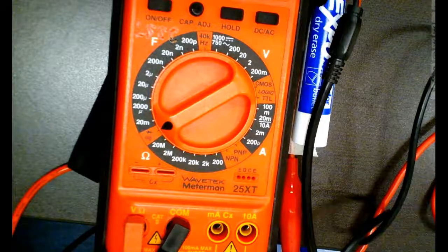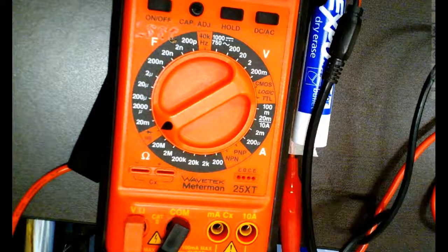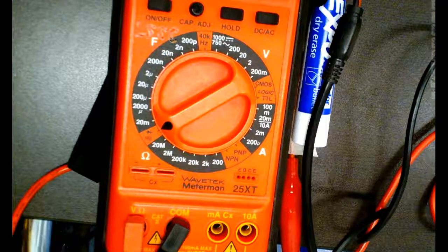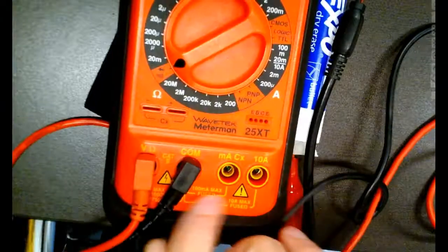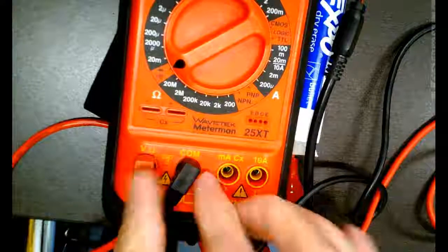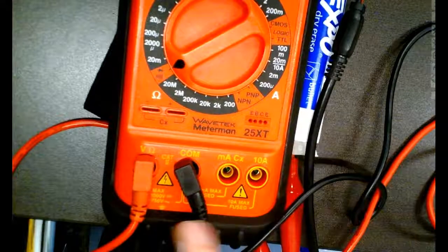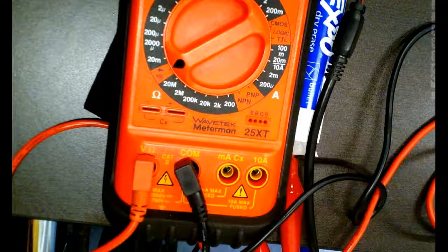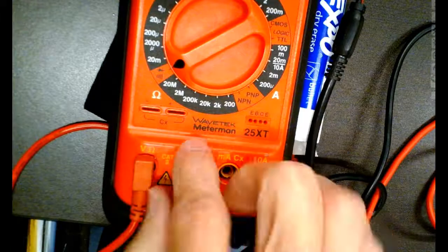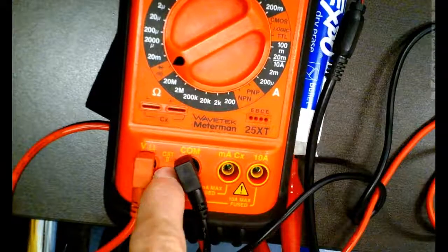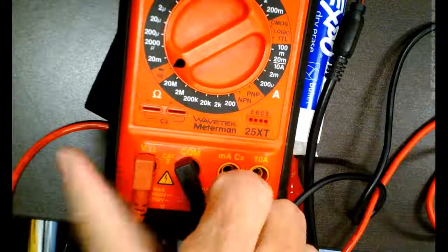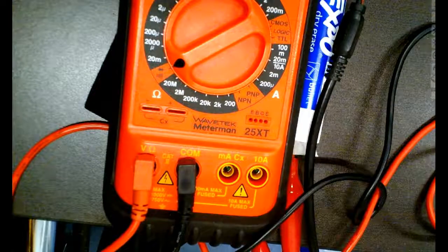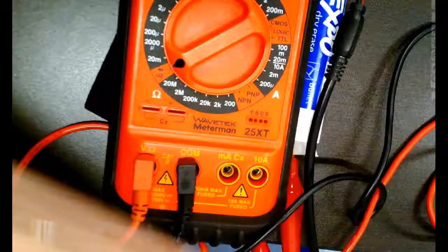This is the meter that Lawson had before we merged. So these meters have been around for a while. But you notice it doesn't have a category rating on it. So this is before 70E came out on these meters. Where do you see Cat 2 at? Oh, sorry, you're right. So this is after, this is a Cat 2 meter. The Sperry that we've had for so long does not have a category rating on it.